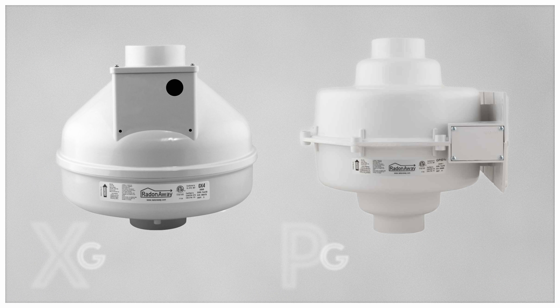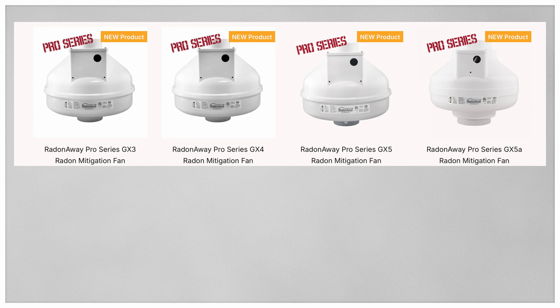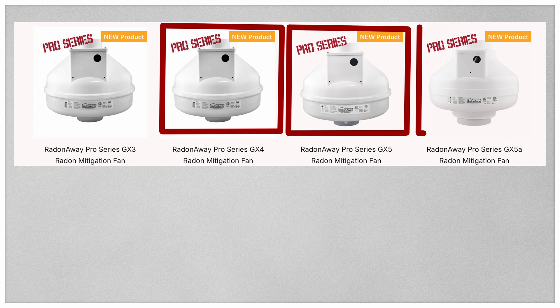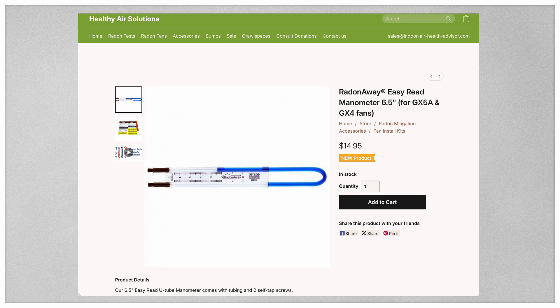Keep in mind that if you are buying a GX series fan as a replacement for a PG fan on an outside system, the wiring is in a different spot and may require a change in fittings. Also remember that the GX4, the GX5, and the GX5A will need a 6.5 inch manometer, and that's due to the high suction of these fans.